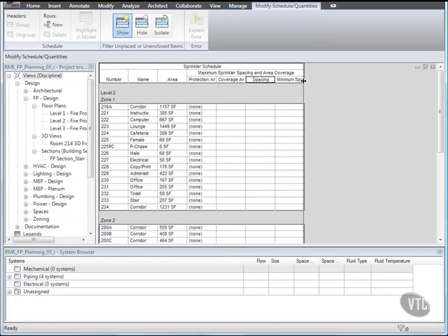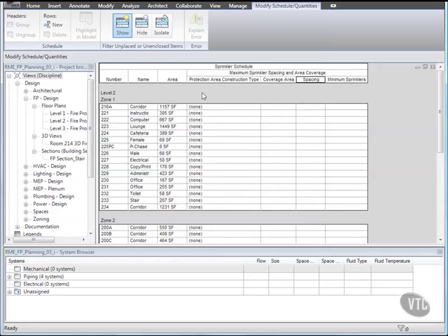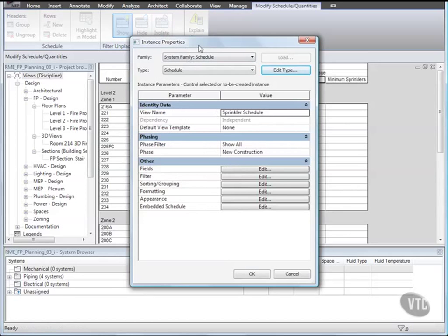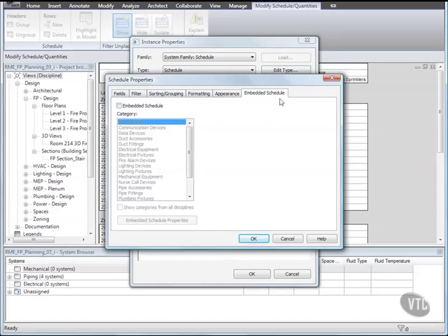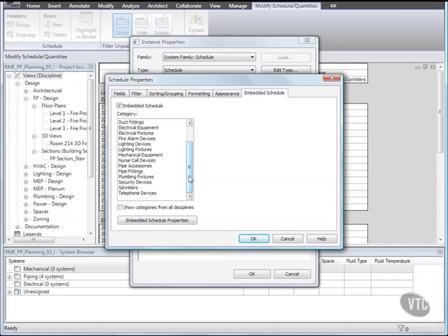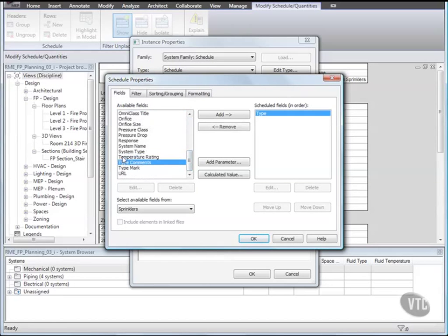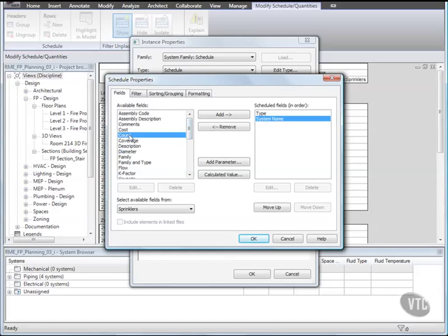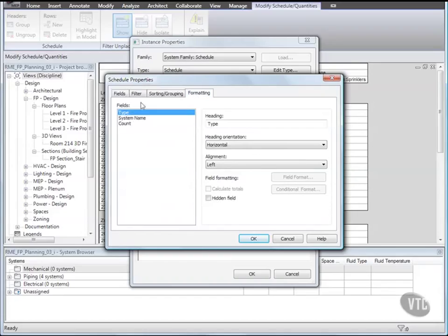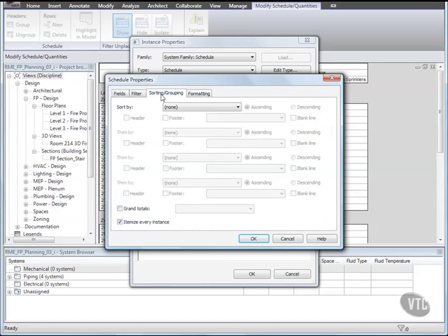Next we'll create an embedded schedule. Right-click in the schedule and click View Properties. And in the Instance Properties dialog, under Other, for Embedded Schedule click Edit. In the Schedule Properties dialog, on the Fields tab, under Available Fields, double-click Type, System Name, and Count. Then on the Formatting tab, under Fields, select Count and under Field Formatting select Calculate Totals. And on the Sorting and Grouping tab, select Grand Totals and then select Totals Only. And click OK three times.